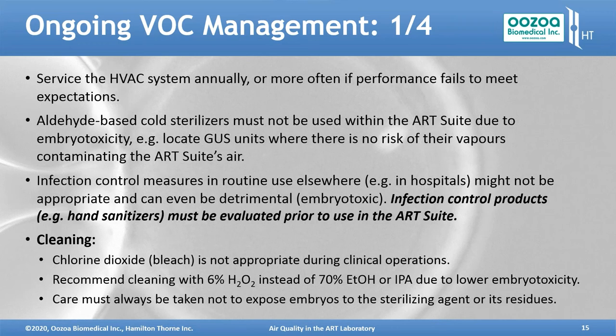You must not use aldehyde-based cold sterilizers within the ART suite. That's anywhere where the air is recirculating that could take those vapors back into the embryology lab, because they are highly embryotoxic. So your GUS units need to be located where there's no risk of their vapors contaminating the area of the ART suite. Infection control measures that might be routine elsewhere, for example, if you're in a hospital, might not be appropriate and can even be detrimental because they're embryotoxic. So infection control products, such as hand sanitizers, must be evaluated prior to use in the ART suite.